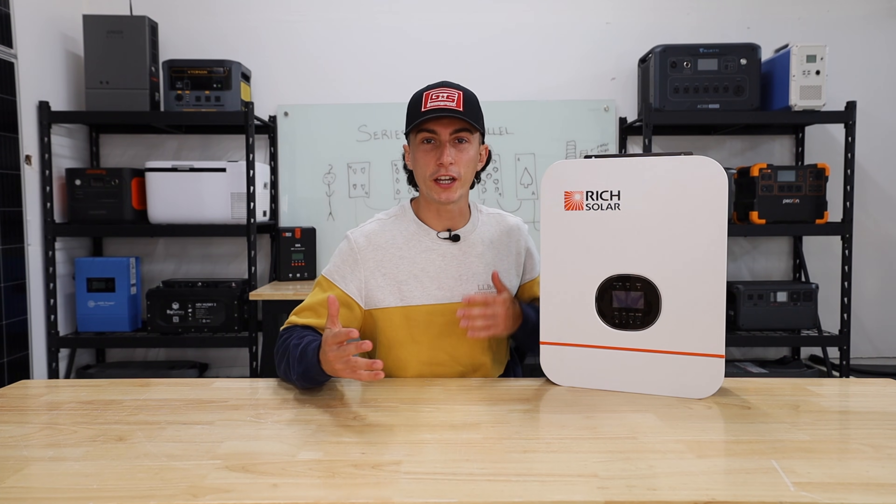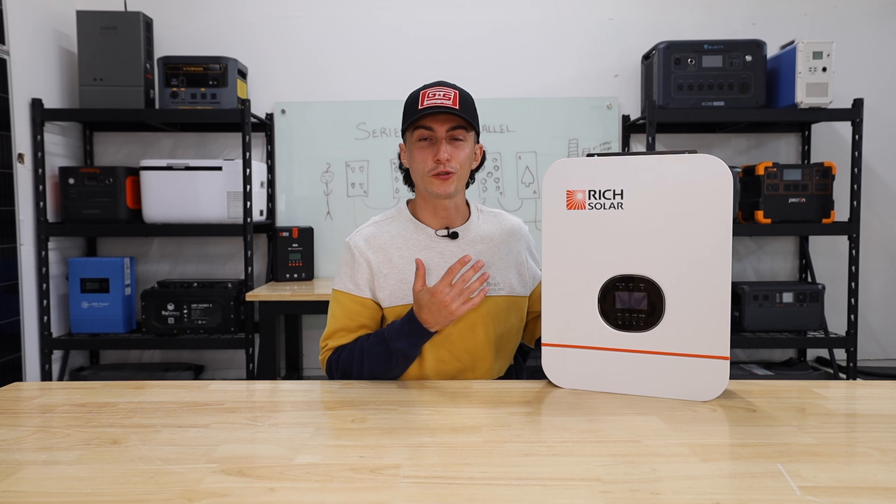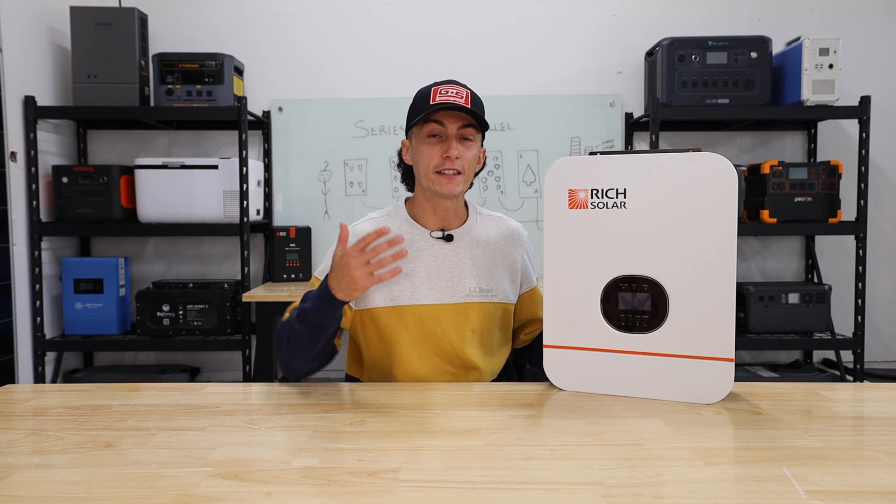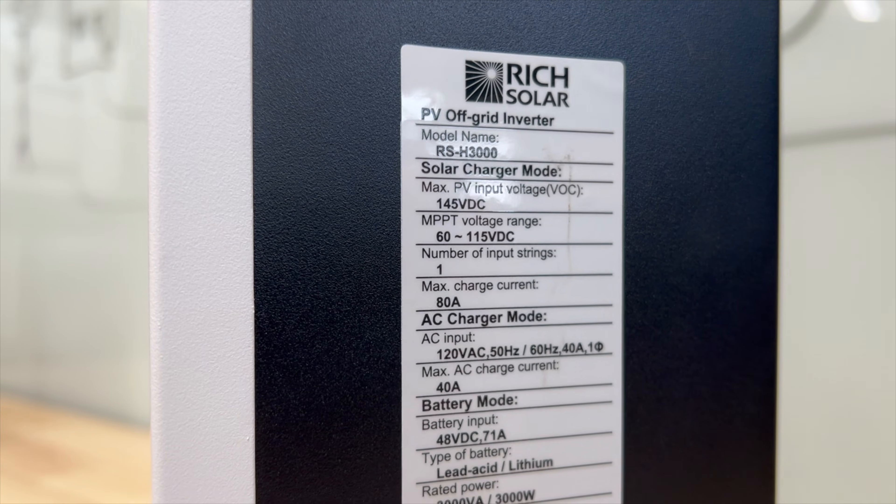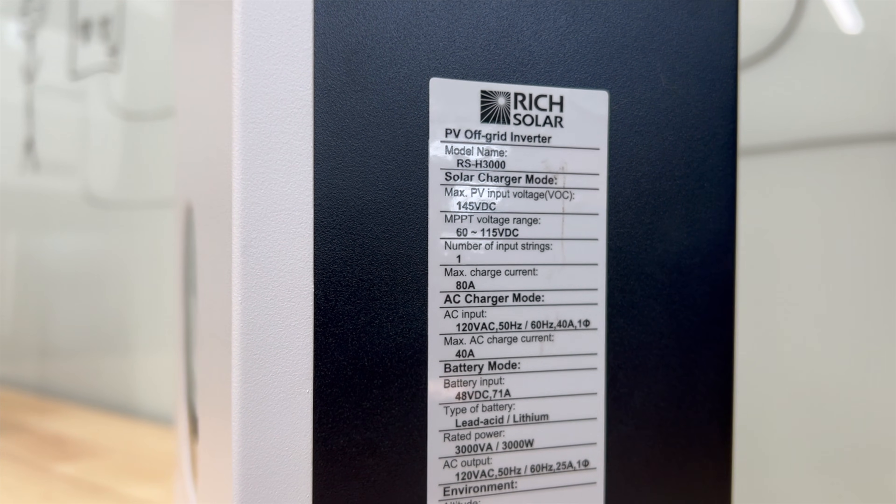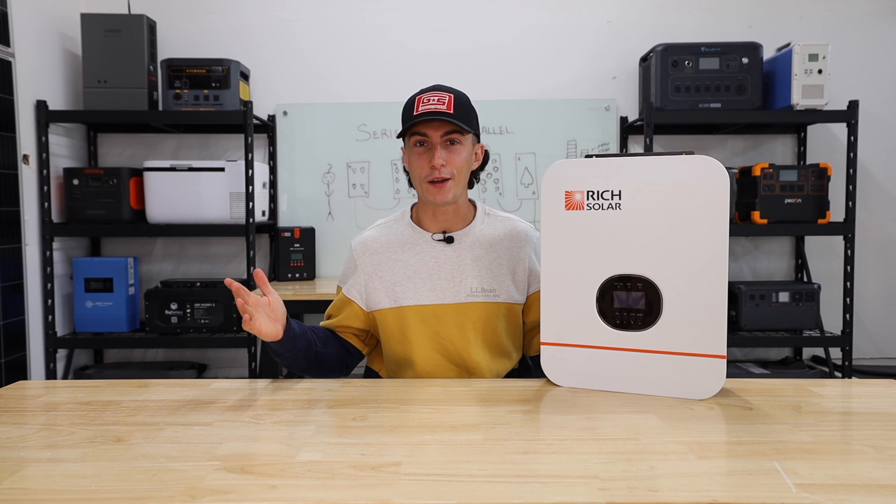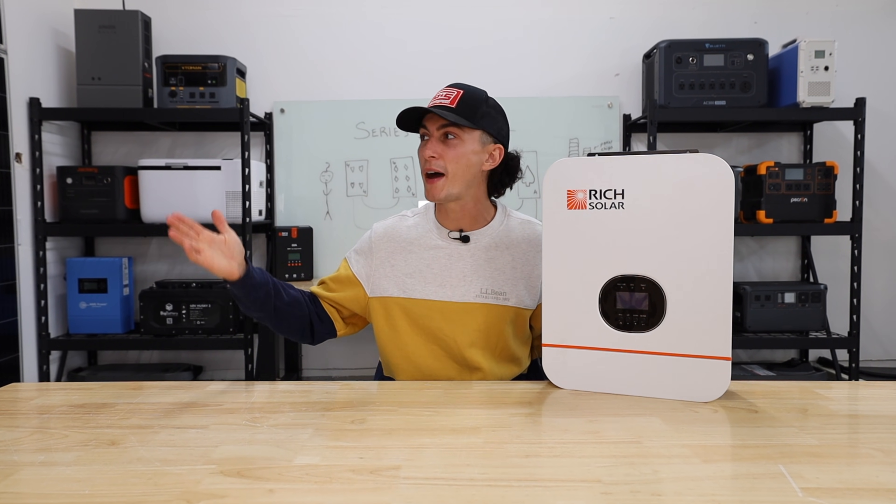If we were to take a look at a real life example, this little Rich Solar 3k inverter has a built-in charge controller with a limit of 80 amps and 60 to 115 volts. So we know we're never going to hit the amperage limit because both our examples, the max amperage we got to was 60 amps.